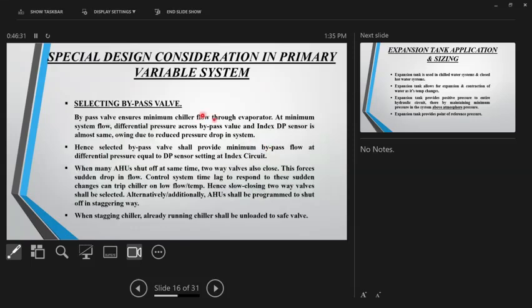Now, how to select this bypass valve, or minimum flow bypass valve? What should be its diameter? I will first only read this, and we'll go back again to that diagram. Bypass valve ensures minimum chiller flow through the evaporator. We all know, nothing great about this. At minimum system flow, differential pressure across bypass valve and index DP circuit is same. I'm sure this must be a bit difficult to understand. No problem. Let us read it again and then go back to that chart. At minimum system flow, differential pressure across bypass valve and index DP circuit is same.